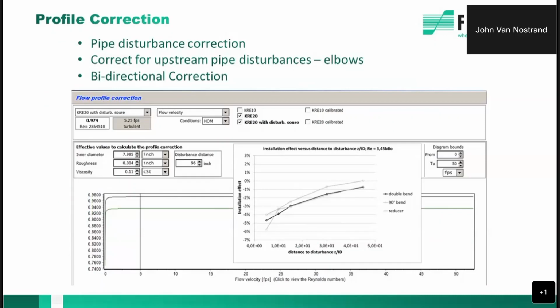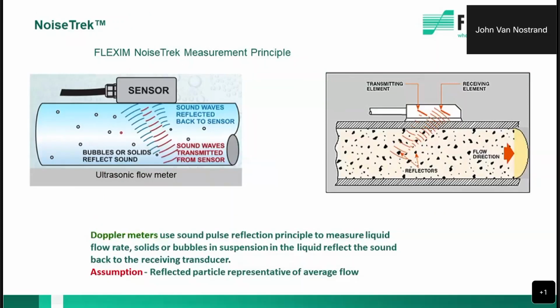So how much can we shorten it? Well, we've done a lot of testing over the years, and we've learned how flow profiles behave and what happens with the introduction of upstream disturbances. And as a result, we have a new feature called profile correction. You can actually program the distance between the elbow and the center of the transducer and correct for the profile disturbance upstream, like an elbow or a 45. So now we don't have to worry about the straight run requirements. We can install in very tight locations.